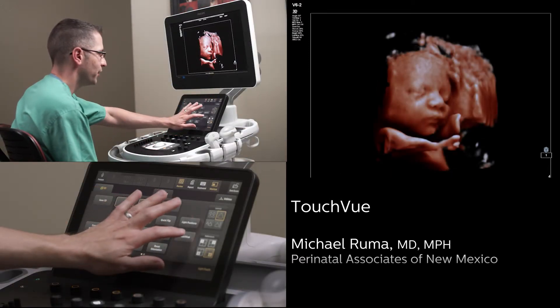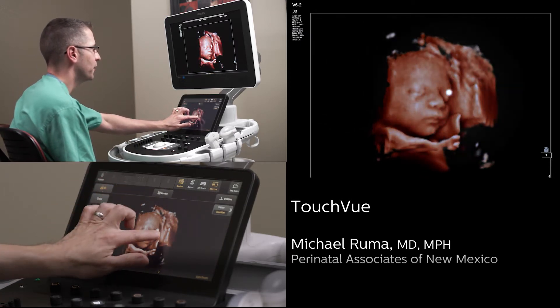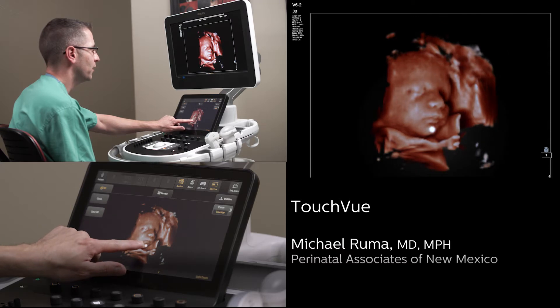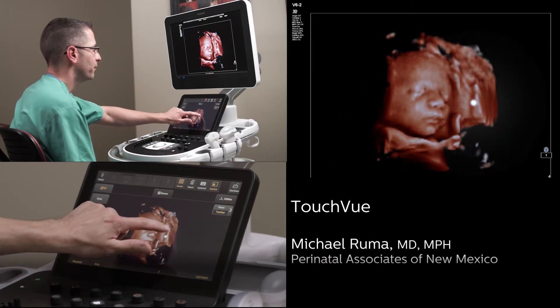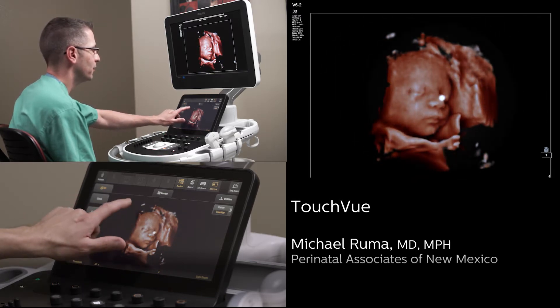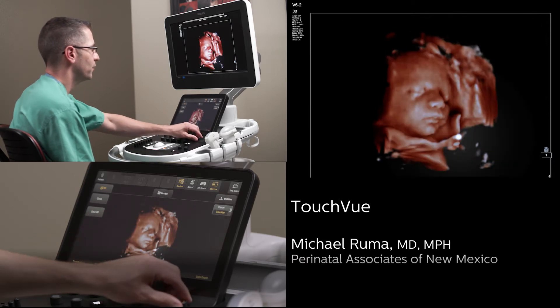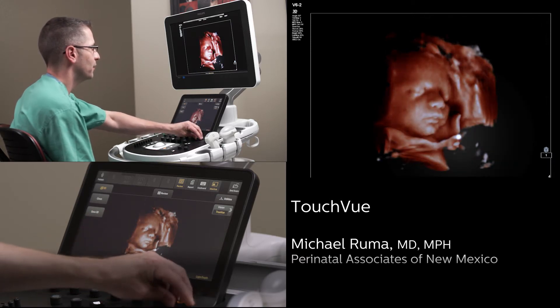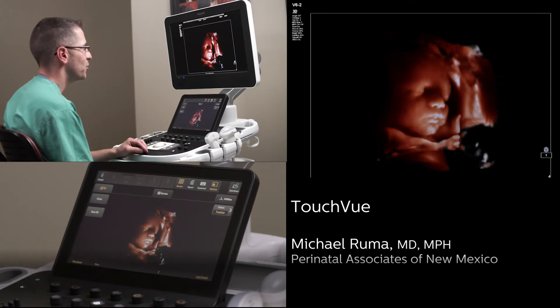We are going to bring up TouchVue to be able to put the light and drag the light for the patient yourself around the volume in an intuitive fashion, just like any smartphone at home. You can double click and place the light in multiple different places, and you can also bring the depth of the light in to provide some unique shadows and illumination to the fetal face.